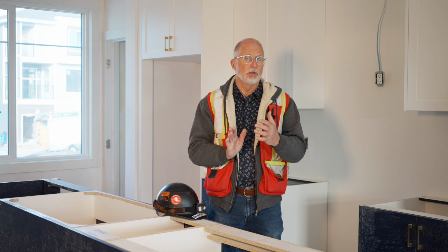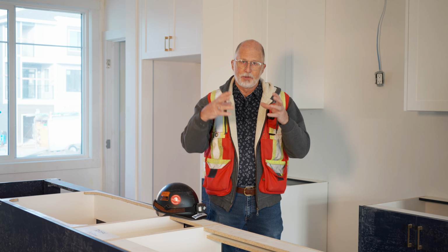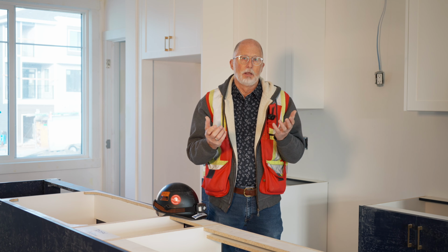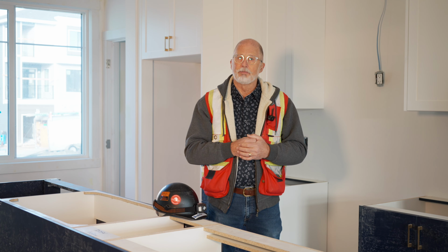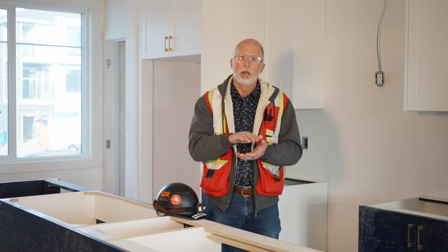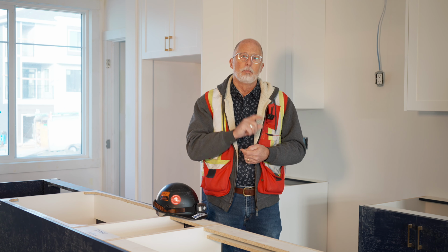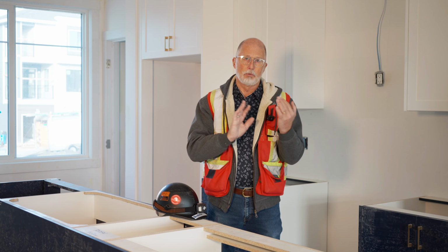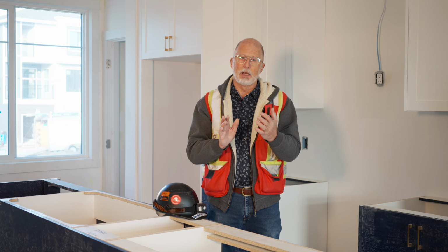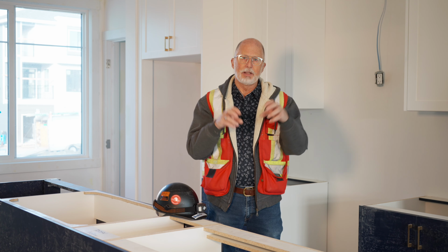Once you're into the middle units now, when you're doing airtightness, not only do you have a smaller space, so probably around 12 to 15,000 cubic feet, so you've cut that volume in half as compared to a single family, so now the number really goes up when you're doing your ACH, but you also have 2 walls to work with. So typically on multifamily, you'll have the end units will be more airtight than the center units.